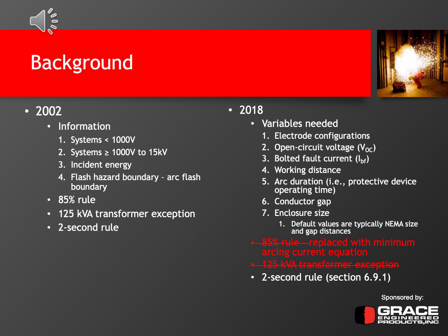2002 also introduced the 2-second rule, which basically says that based on the configuration of the equipment and the enclosures and where the person is going to stand, if it's feasible, or an engineering decision is made that it's feasible, for a person to remove themselves away from the hazard of an arc flash within 2 seconds, then the incident energy calculation can be cut off at 2 seconds. This holds even if the circuit breaker or fuse, whatever the protective device is, wouldn't operate for an hour or 5 hours or a week from the actual incident of the arc flash due to its installed protection settings.